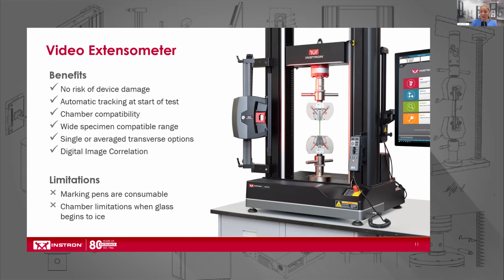It can be configured to cover a wide range of specimen gauge lengths and elongations, and it's a great alternative to purchasing and maintaining multiple clip-on devices because it has the ability to consolidate all of those applications into one device. Applications from sub-sized metallic specimens to high elongation rubbers can be covered in one device, unlike clip-ons where you're probably going to have to stock at least two to accommodate that range of testing.